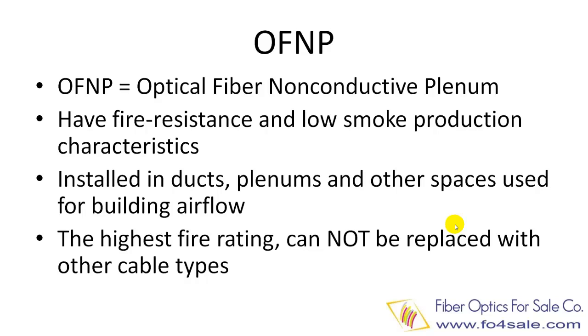Based on the above, we are coming to the fire ratings for fiber optic cables. The first fiber cable rating is called OFNP. OFNP stands for Optical Fiber Non-Conductive Plenum. Non-Conductive means the fiber cable has no metallic components. The plenum part means this cable can be used for plenum areas. OFNP cables must be fire resistant and produce low smoke when on fire.